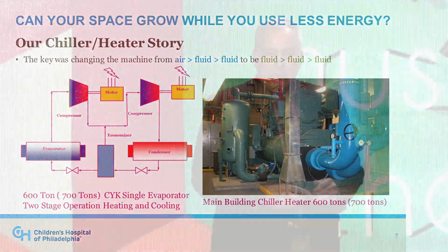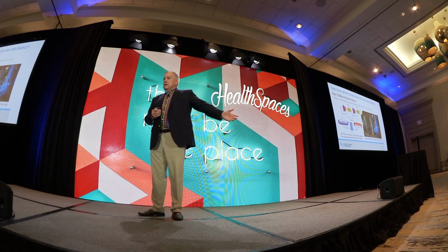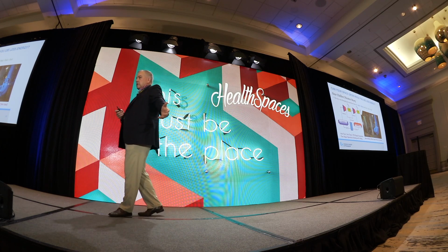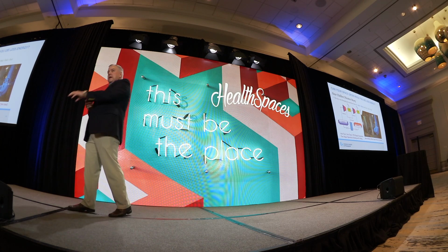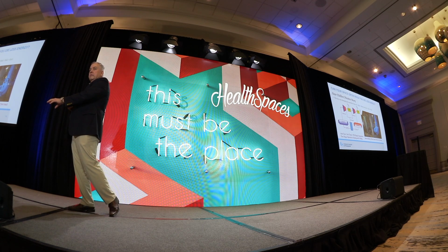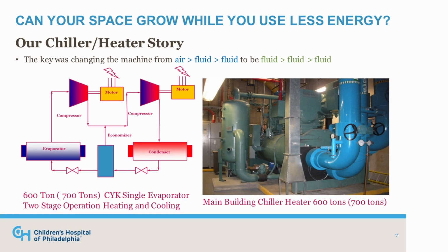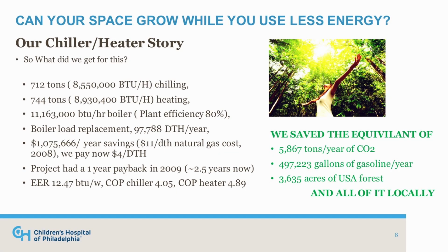It's a 700-ton CYK chiller, and what it does for an architect is it takes BTUs out of our chilled water return system and dumps them into our reheat hot water system. It's got 175% efficiency, and it cost about $1 million, with a 1-year payback at our then energy cost. That's a photograph of it on the right-hand side, and you're all welcome to come see it, but York, the CYK chiller, they'll be happy to sell you one.